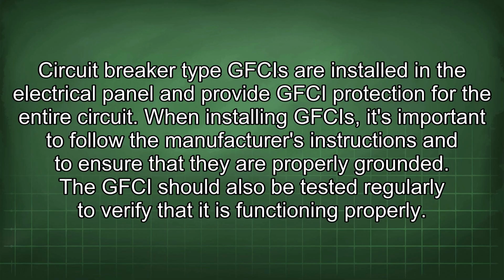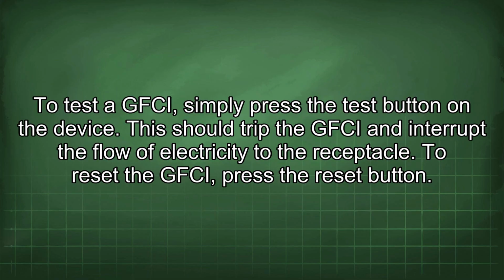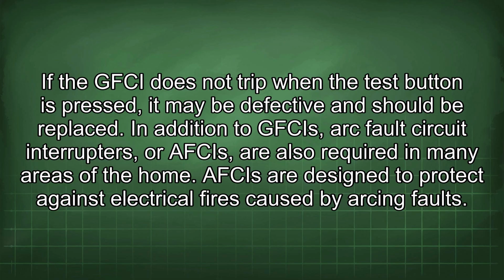When installing GFCIs, it's important to follow the manufacturer's instructions and to ensure that they are properly grounded. The GFCI should also be tested regularly to verify that it is functioning properly. To test a GFCI, simply press the test button on the device. This should trip the GFCI and interrupt the flow of electricity to the receptacle. To reset the GFCI, press the reset button. If the GFCI does not trip when the test button is pressed, it may be defective and should be replaced.